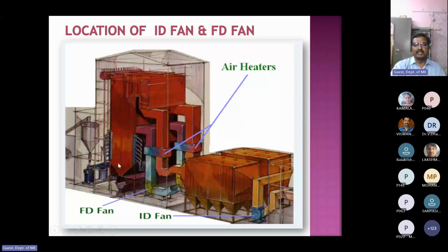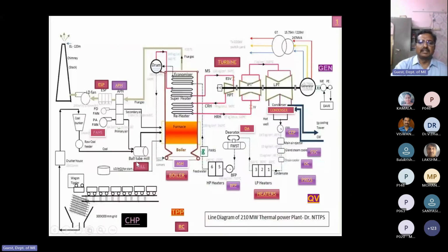The FD fan, ID fan, or PA fan takes air from the atmosphere. It may contain some moisture also. So to remove that moisture, we have air heaters, which are called air preheaters. With the help of the air preheaters, the primary and secondary air are heated up. Here the heating source is flue gas. Flue gas after the economizer flows in one direction and air from the FD fan and PA fan flows in the other direction and gets the heat from the flue gases. So these are all the fans. And after that, it goes to the boiler.